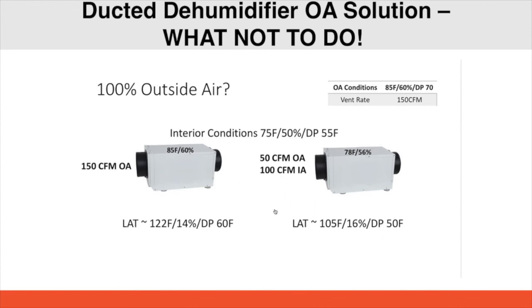And again, if we look down below here at our outputs, if we just do it at the conditions up above of a 70 dew point, we're only decreasing that dew point to 60 if we're using it for 100% fresh air. Now, if we set it up to bring in 50 CFM of fresh air and pull 100 CFM from the indoors, from our return, this allows us to get that dew point down to 50. So it's far more effective to set it up in our recommended install than it is for 100% fresh air.